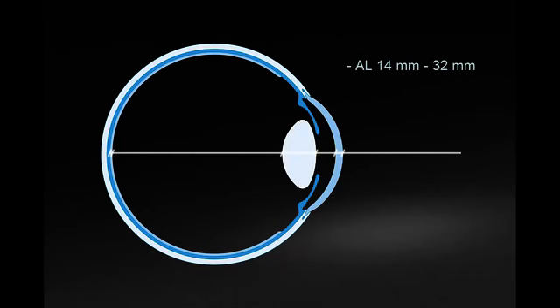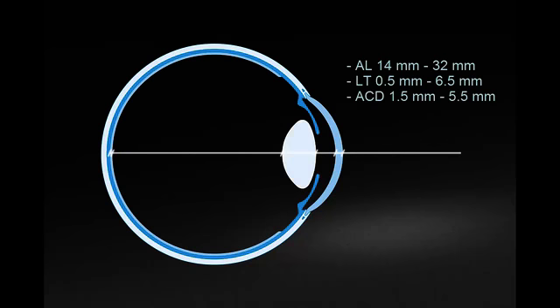The measurement range for axial length is 14 to 32 millimeters. For lens thickness 0.5 to 6.5 millimeters, ACD 1.5 to 5.5 millimeters, and for CCT is 300 to 800 microns.